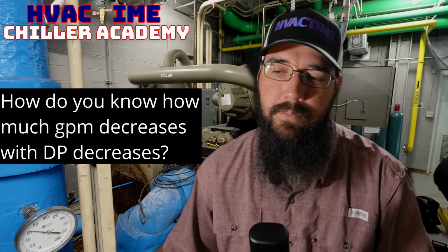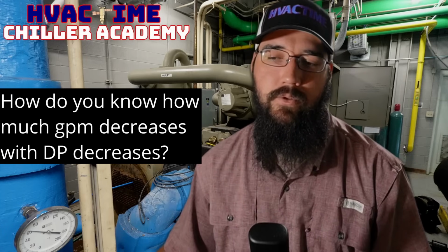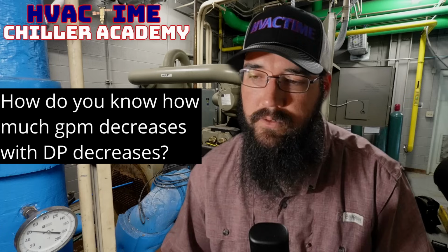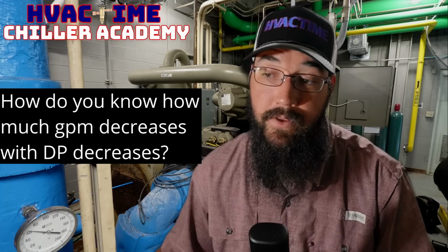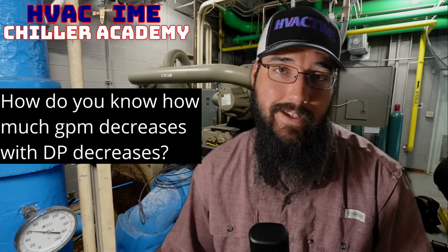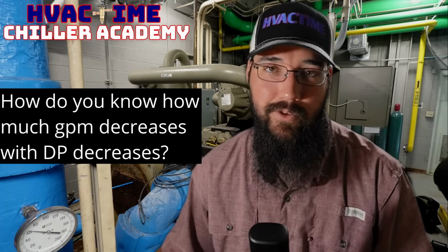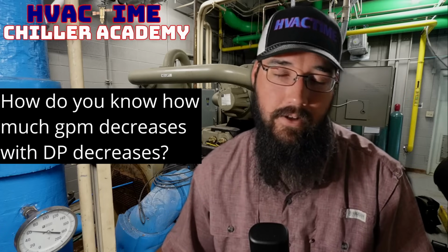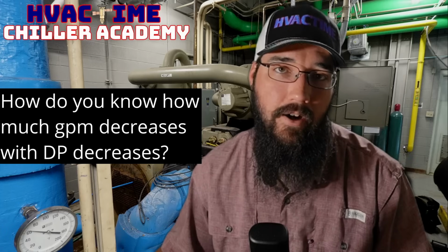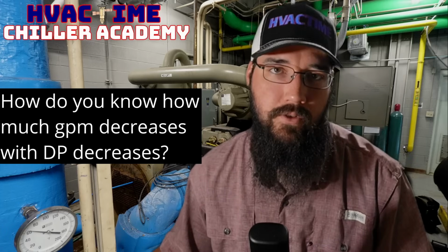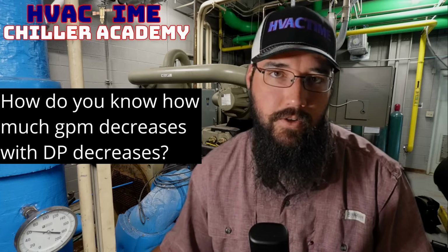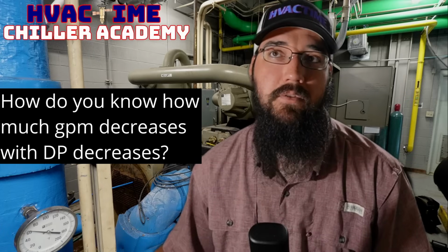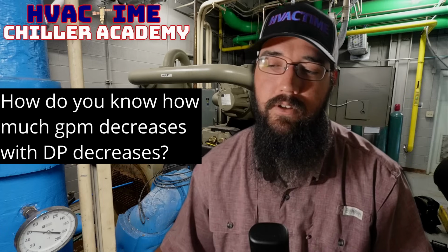That's going to very specifically depend on the actual heat exchanger and its flow design. I do want to clarify one thing: talking water on these hydronic heat exchangers is talking refrigerant. They're directly tied into one another. It's like talking air to the refrigerant circuit in a split system or an RTU. It's the exact same conversation and concept in theory.